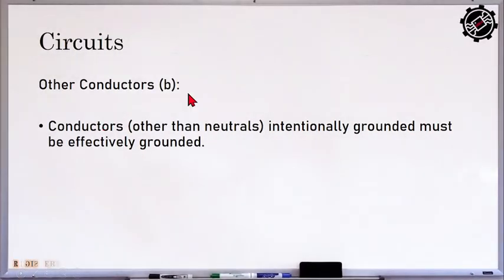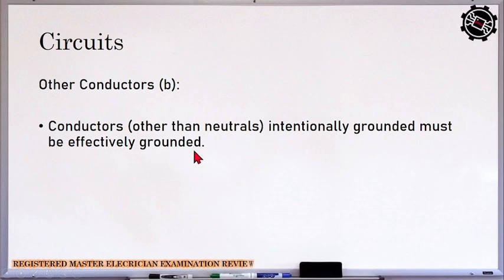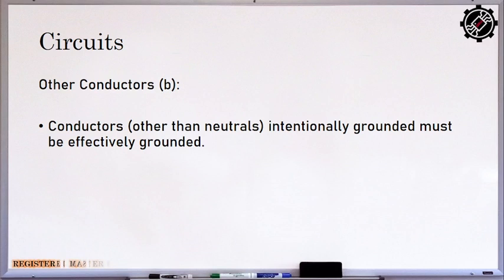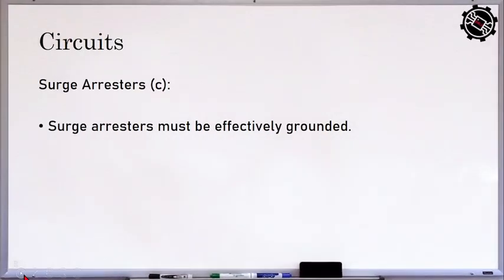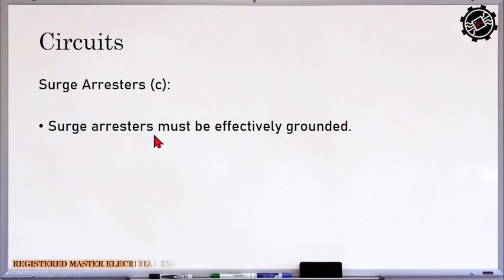Okay, so other conductors. So other conductors other than neutrals intentionally grounded must be effectively grounded. So if our grounding system, our grounding wire must be grounded, no, must be connected to ground, no? Tapos yung neutral, no, or yung common point ng ating system, if we will have a three-phase Y system, so it must be grounded also. Okay, so surge arresters. So surge arresters must be effectively grounded. So all surge arresters must be connected to the ground.